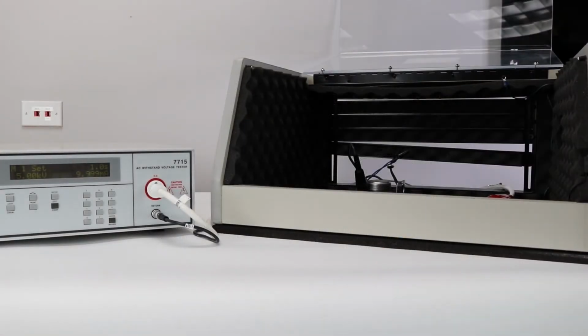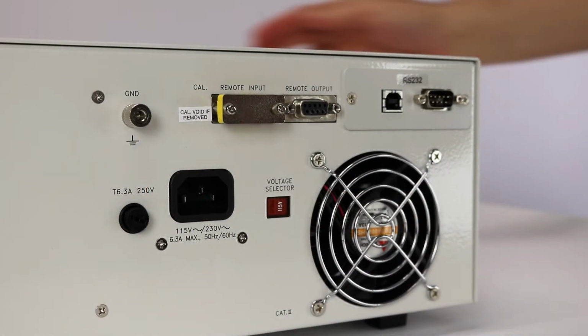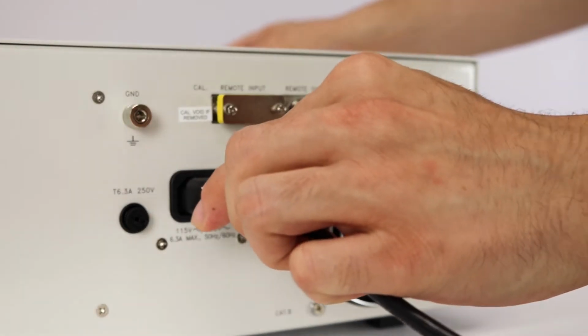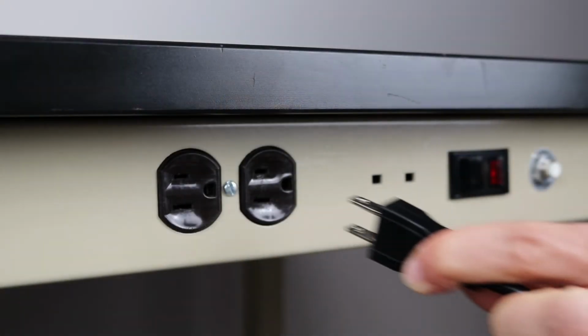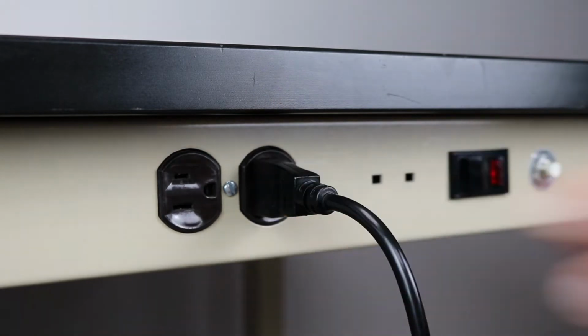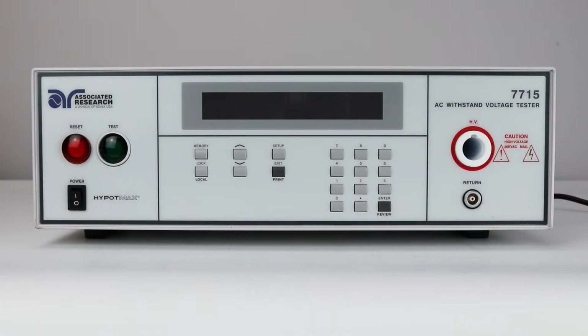This allows the user to wire the instrument to the doors of a DUT enclosure for an extra measure of operator safety. This is also a safe workstation best practice. Connect the power input plug into its socket on the rear panel of the instrument. Connect the male end of the plug to the outlet receptacle. Turn on the power switch on the front panel of the HypotMAX instrument. It will automatically navigate to the Perform Test screen.